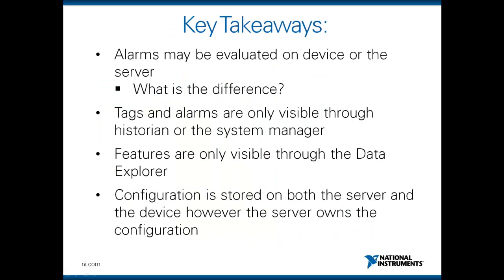A couple of key takeaways, just to sum up what was on this slide. One, alarms can be evaluated either on the device or the server. Just to rehash, if a cRIO is publishing tags to the server, we can create alarm rules off of those tags. However, we can also push alarm rules all the way down to the cRIO, and the cRIO can evaluate alarm rules and instantiate alarms himself.